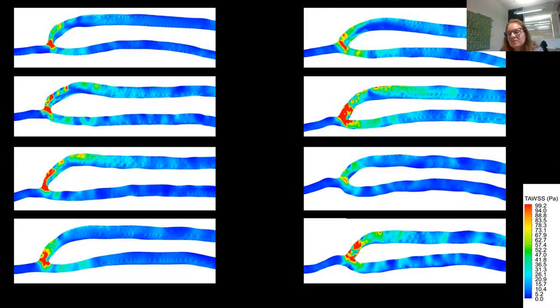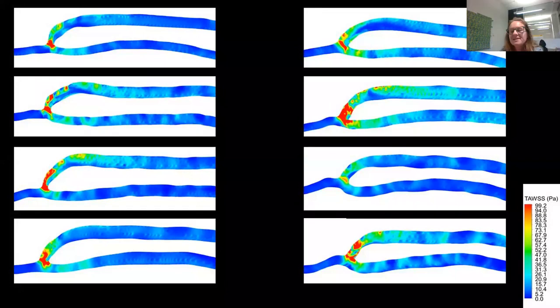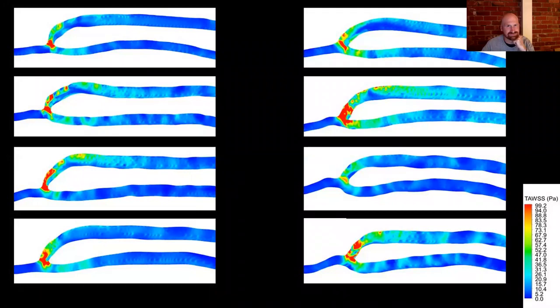And even when we look, the stent strut should be perfectly circular because it's made from wire. In our segmentations, they're not perfectly round. So we know that it hasn't been made completely correctly. We could go back and try and turn them all into round. But one of the things we've been looking at is how many points we get around the strut. Because obviously if you only put like 10 points around, then you're not getting a circle at all. So yeah, it's a very difficult one to do.